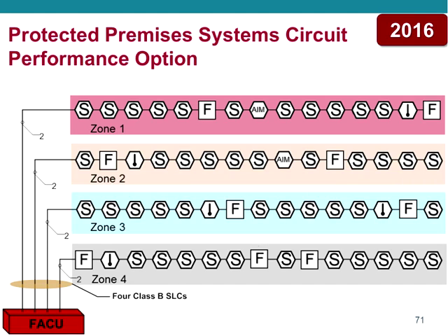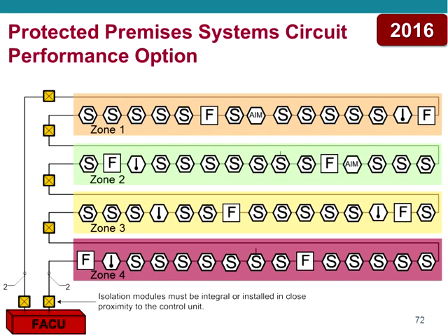Now this obviously is going to be a bit pricey, because now you have to have a larger control unit or a control unit with more capacity. Most of the control units you buy for a 3 to 4 story building would only have 2 zones on it, or maybe even 1 zone, 1 SLC. So what do we do? Well, there are other ways around it, so let me show you some of those.